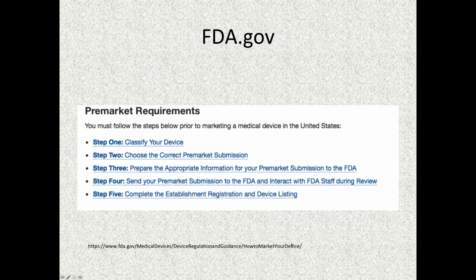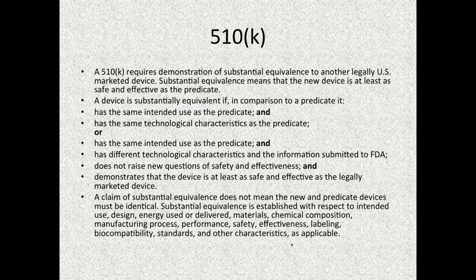But you should know that the devices under the 510K are not approved for market, they're cleared to market. And the assumption is that under the 510K, your quality system is already in place. So for a medical device that meets the 510K requirements, you have defined the packaging, the labeling, the sterilization method. You've tested all of those. You've tested your manufacturing process is set, your design is frozen, and your quality system is in place. And if those are not met, you still cannot market your device.